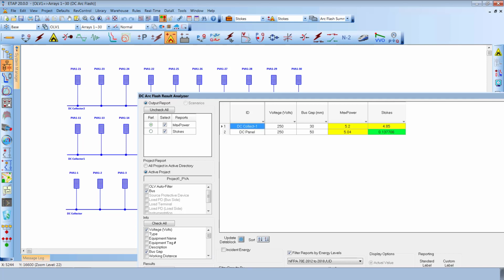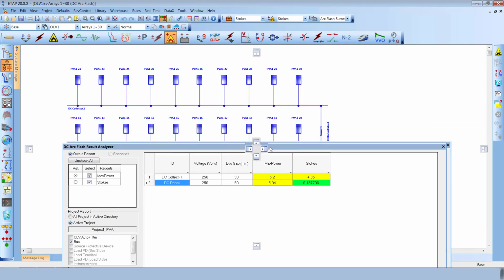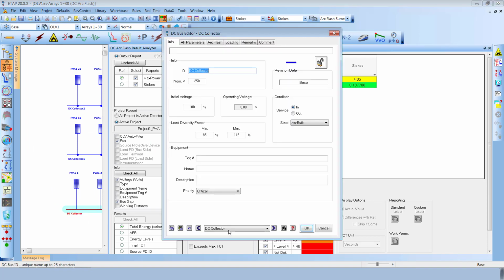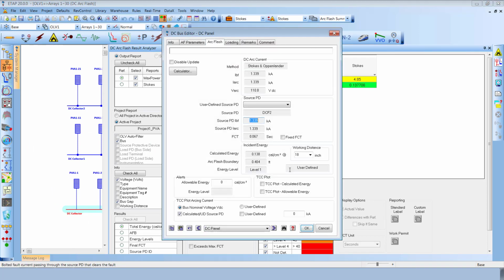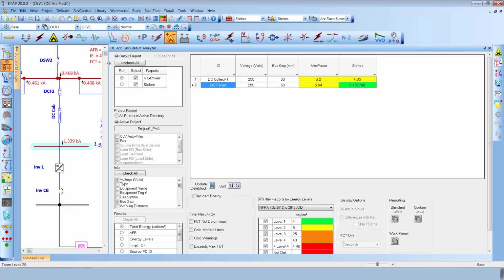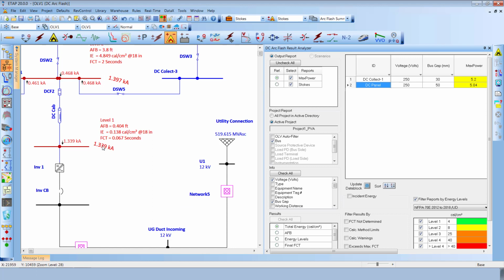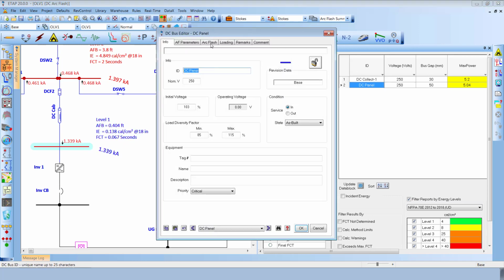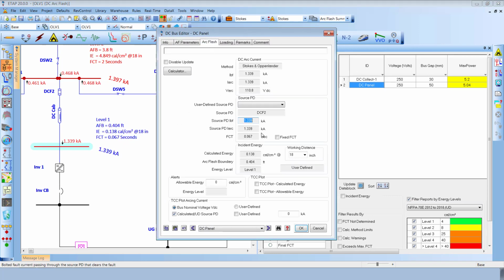Based on the concept discussed on the double iteration technique, let us take a look at the DC panel location and examine the actual arc current results for the Stokes and Oppenlander method, and then compare it against the actual time current curves and see how the arc current calculation resulted in a quicker clearing time compared to the maximum power method.